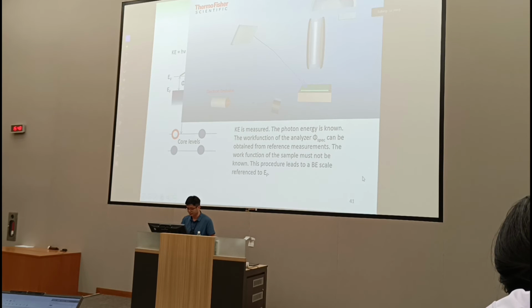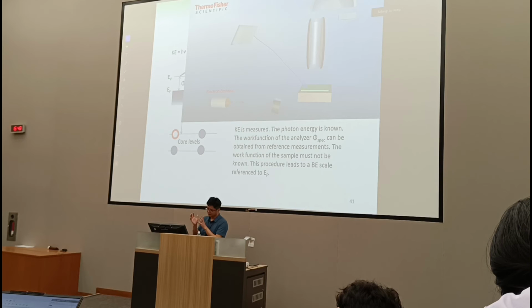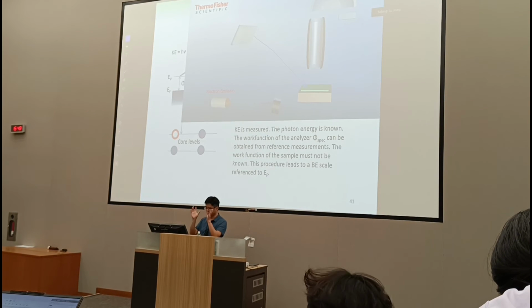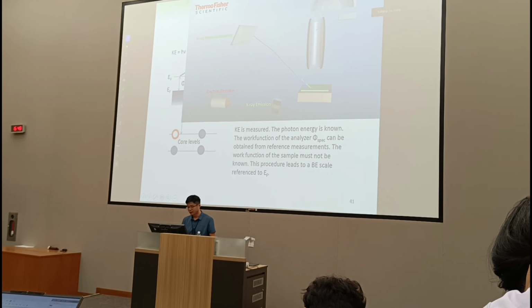They will excite the electrons into your detector, analyzer, right? So here the X-ray first goes through this monochromator that selects just the photons with exactly identical energies before hitting the samples. After that, you create your photoelectron emission and it enters the analyzer, from sample to analyzer.